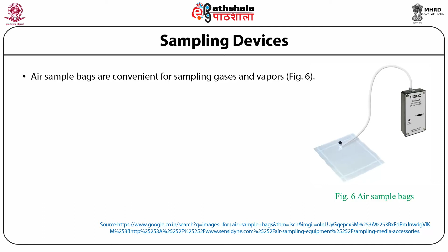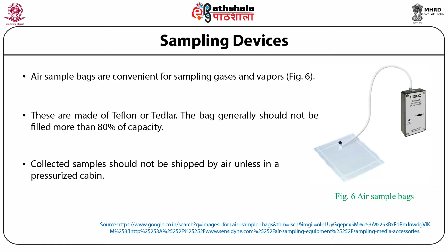Air sample bags are convenient for sampling gases and vapors in which the analyte concentration is well above the detection limits of the measuring system. These are made up of Teflon and Tedlar. The bag generally should not be filled more than 80% of the capacity. Collected samples should not be shipped by air unless in a pressurized cabin. The reduced barometric pressure could cause the bag to burst.